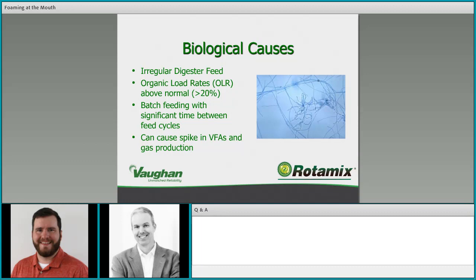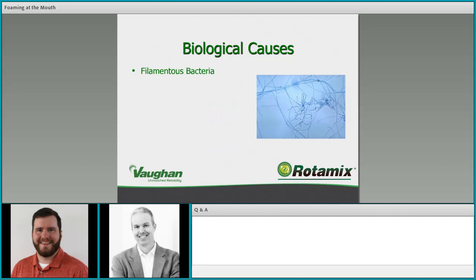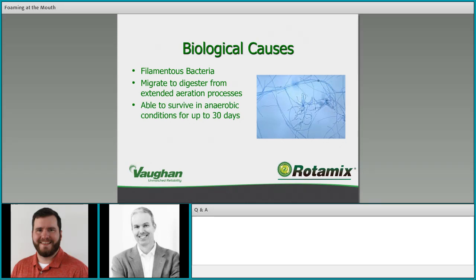Those imbalanced feed cycles can lead to swings in VFA production and gas production that create the conditions for foaming — as well as other issues like pH swings and digester volume problems. Another biological issue is filamentous bacteria, which has a physical aspect in how it interacts with surface tension and bubble stability. From a biological standpoint, they migrate to the digester from an extended aeration process and are able to survive in anaerobic conditions for up to 30 days.